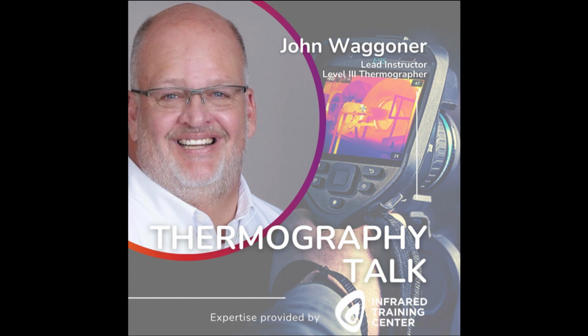Remember that qualified personnel too must be trained on all test equipment. They have to know how to test for the absence of voltage. They need to know how their test equipment works and to be able to interpret the data that particular piece of test equipment provides. And then finally, they also need to know the limitations of each piece of test equipment they operate when electrical equipment is open, energized, and exposed.